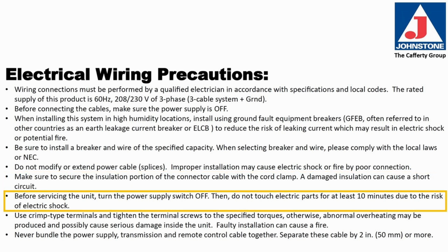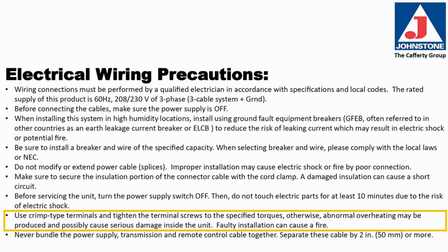Before servicing the unit, turn the power switch to off. Then, do not touch the electrical parts for at least 10 minutes due to the risk of electric shock, since they will hold power in the capacitors. Use crimp-type terminals and tighten the terminal screws to the torque spec specified in the installation manual. Otherwise, abnormal overheating can cause serious damage to the inside of the unit. Faulty installation can cause a fire.